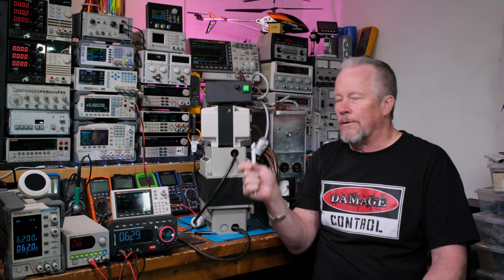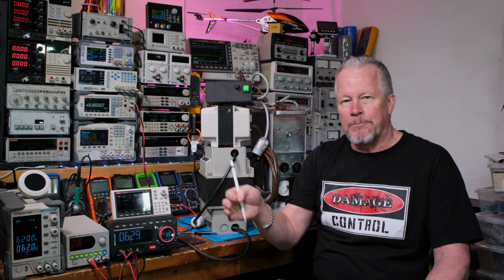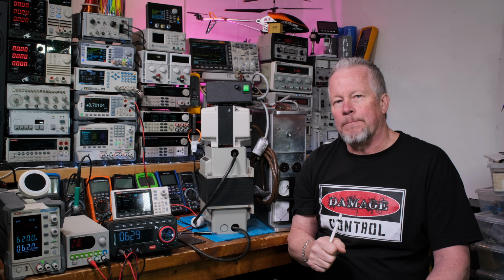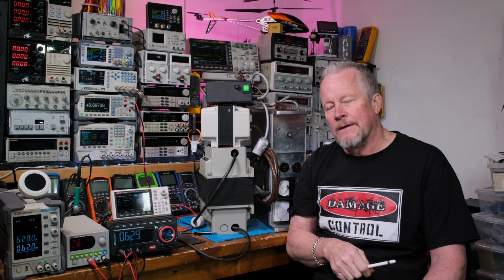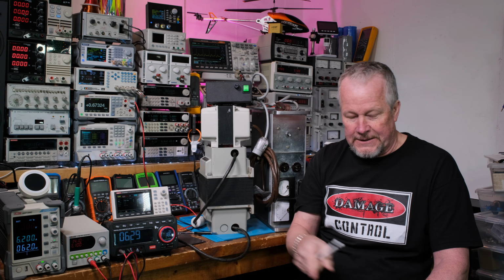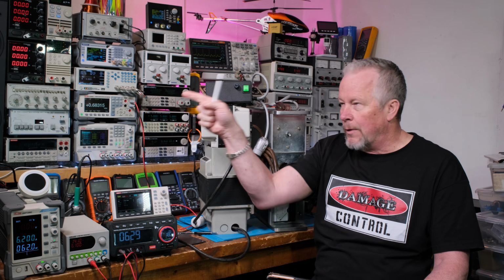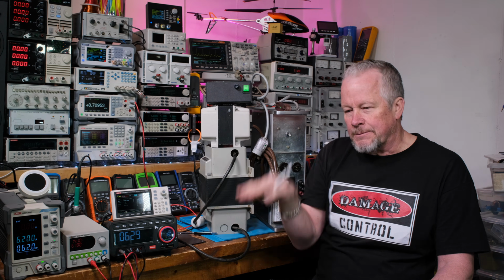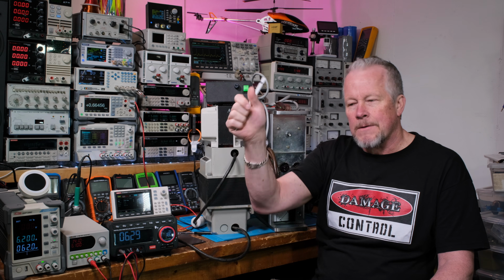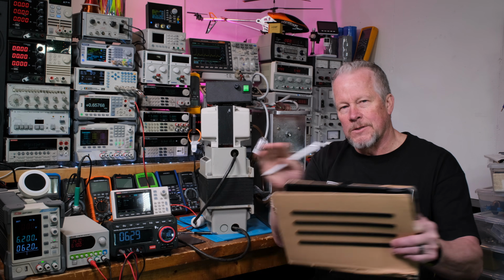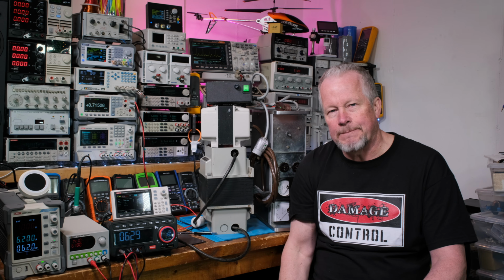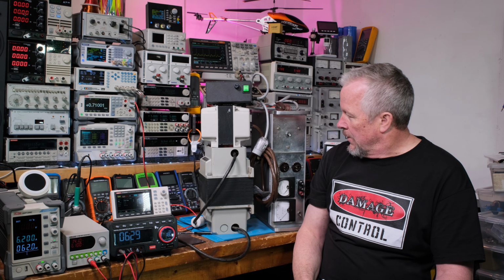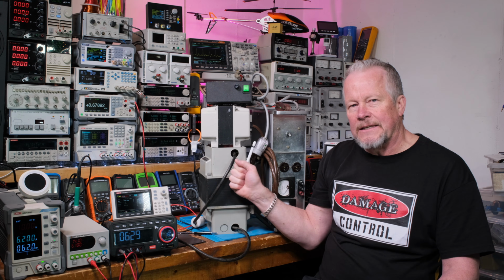So the third wire makes things safer because it doesn't carry any current unless there's a fault. Then it's in play, giving a place to route the current back to the breaker because it's tied to neutral way back there. It jumps down on the green wire, shoots across, and pops the breaker. So that's the whole concept: we want these chassis tied to that same reference.